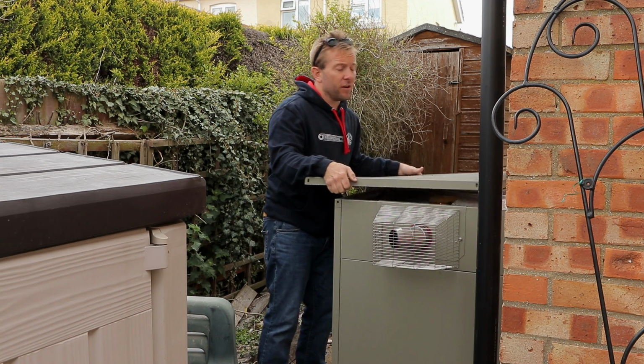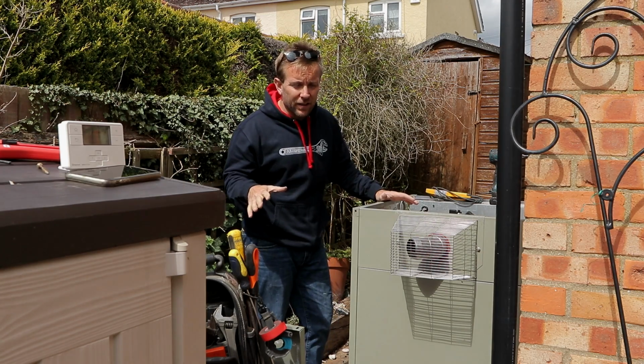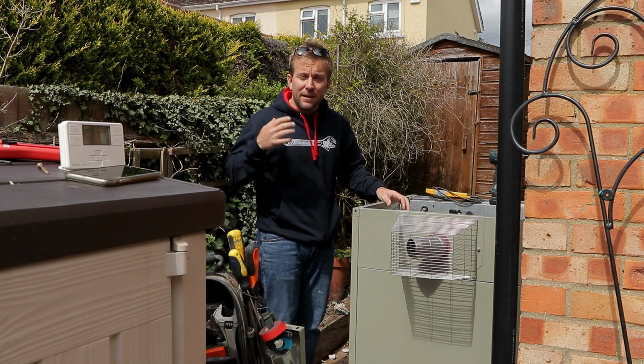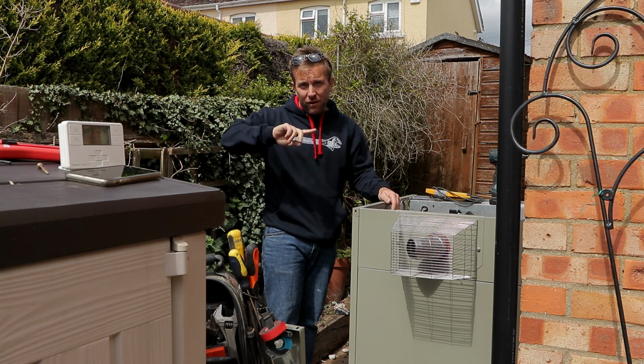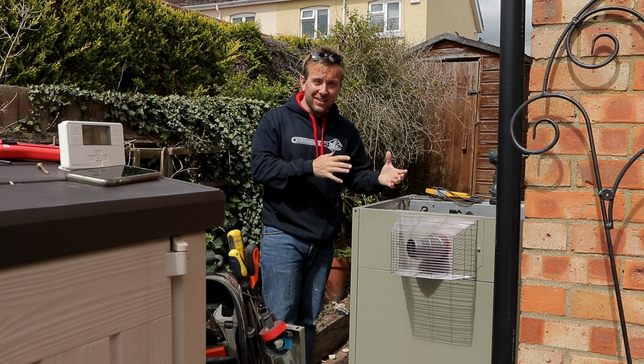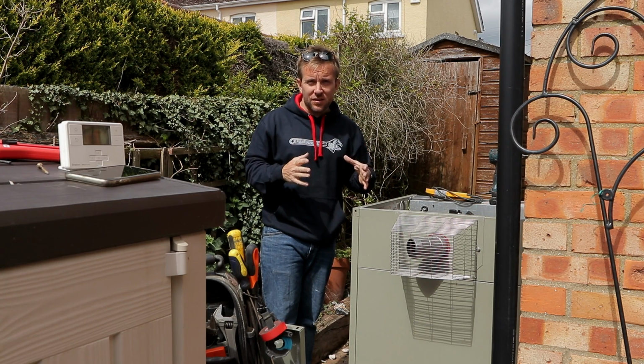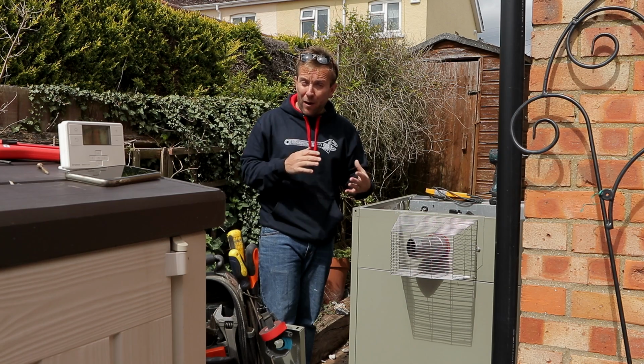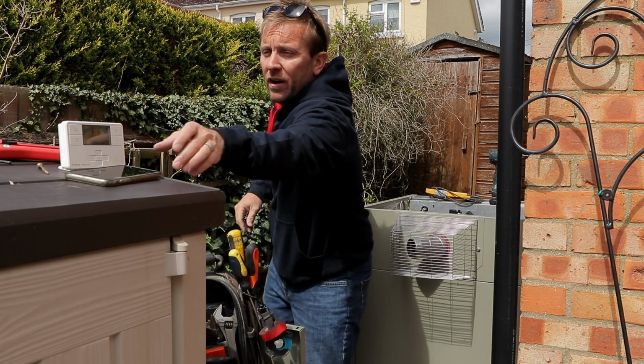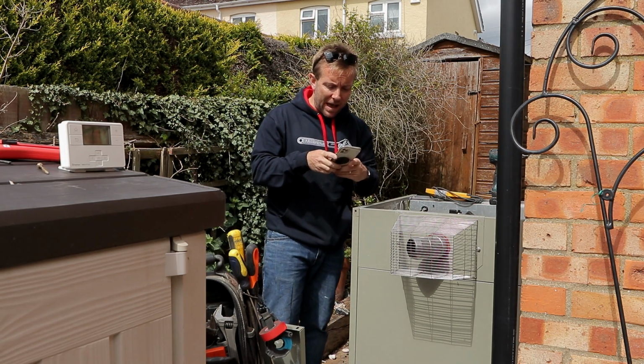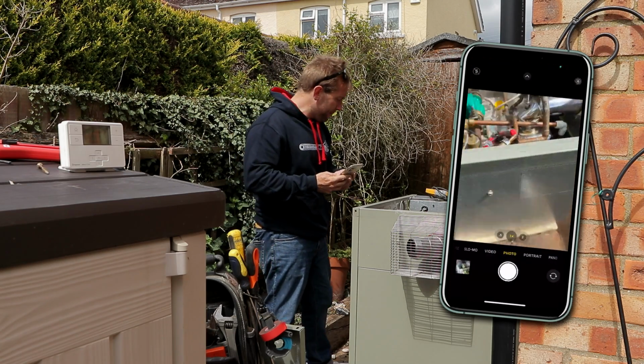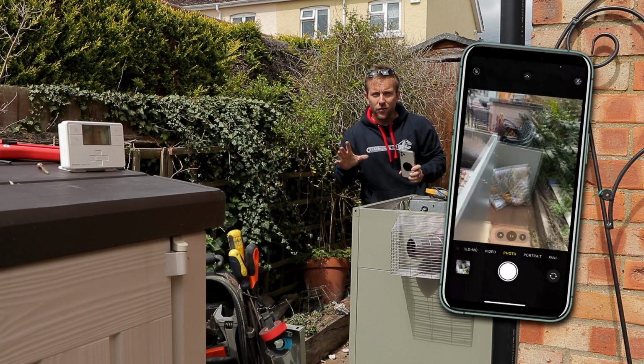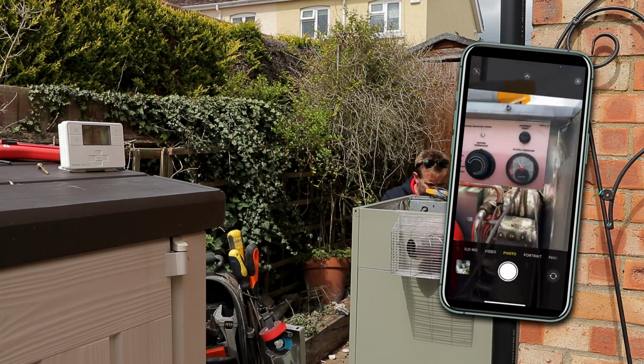Now we've got a pressurised system here. The boiler's running at the moment, and the main symptom we're seeing is a rise in pressure on the heating side of the boiler system. This should actually be a static pressure of about 1 bar. So what I usually do, just to make sure I'm not going mad, I line up my phone as best I can to the front of this.